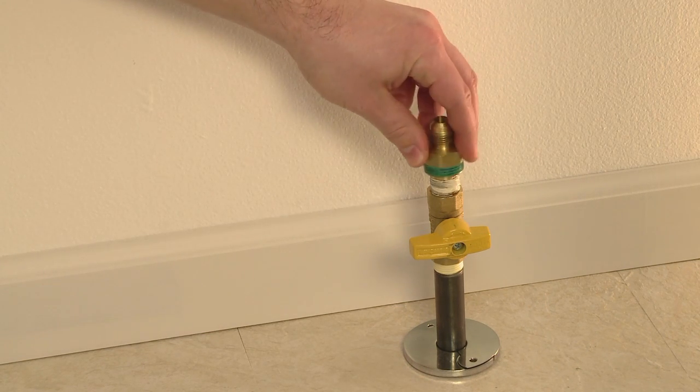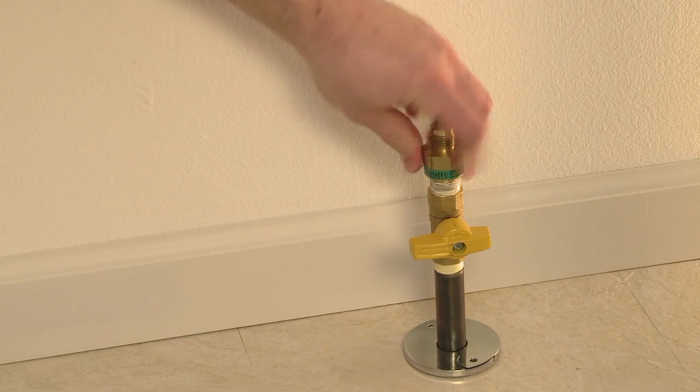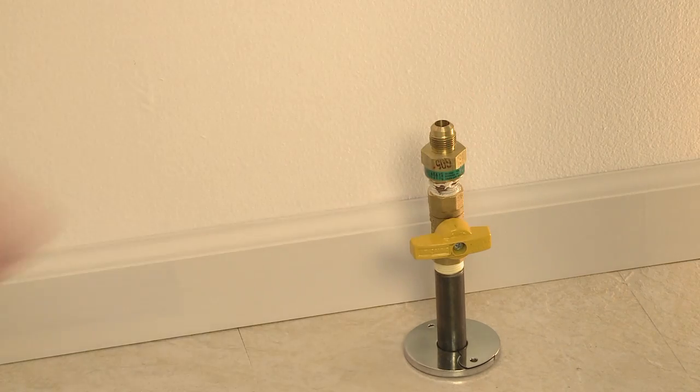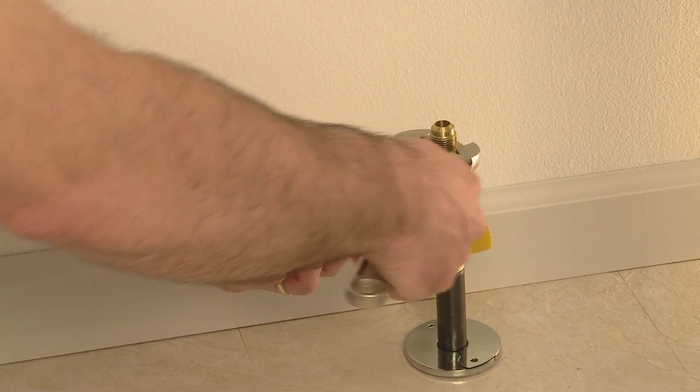Thread the excess flow valve onto the gas ball valve making sure that the arrows on the gas safety valve are pointing in the direction of intended gas flow. Tighten by hand. Place one wrench on the shutoff valve and wrench tighten the excess flow valve with the second wrench.